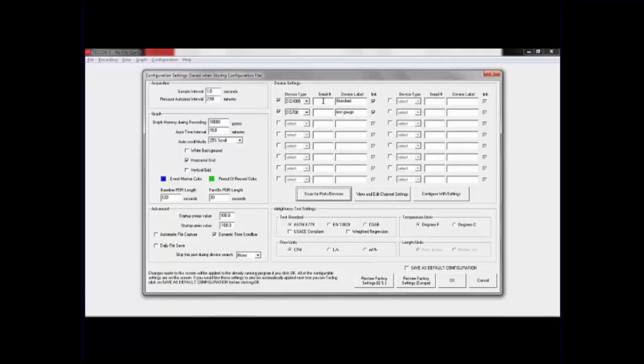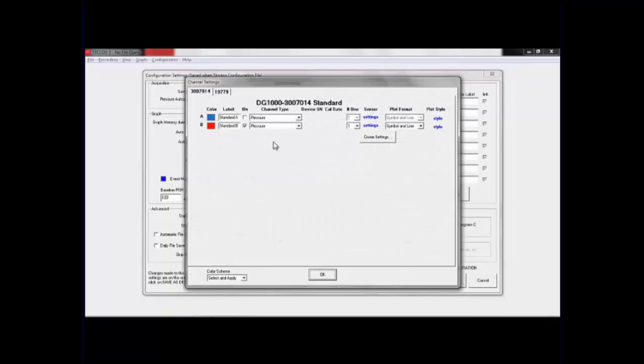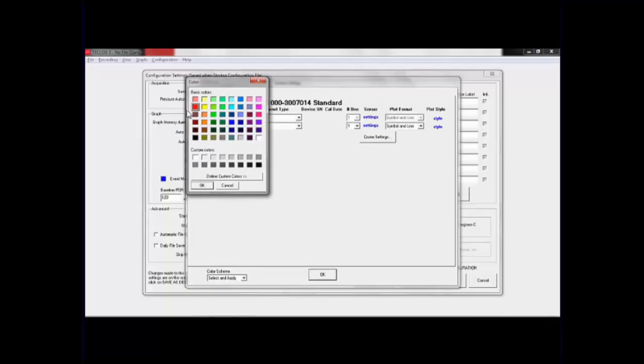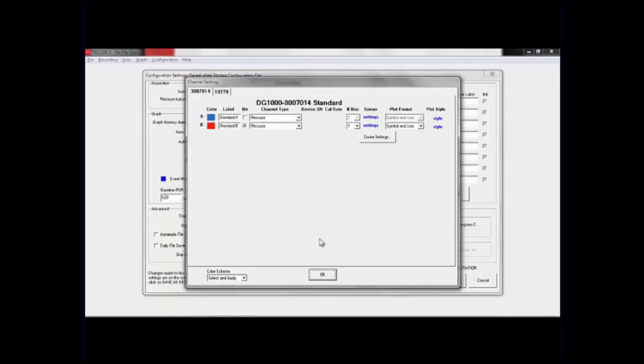Now up in the serial number box, I'm going to double click, and it's pulling up our DG1000 as our standard. We labeled it as standard, and our DG700 is our test gauge. We labeled it as test gauge. And then I'm going to click on the view and edit channel settings, and you can see the two gauges are up here. We turned off one channel. We labeled it standard B, so that's our standard gauge channel B, and we left it as a pressure, and we can choose what colors we want here. We want it to graph.